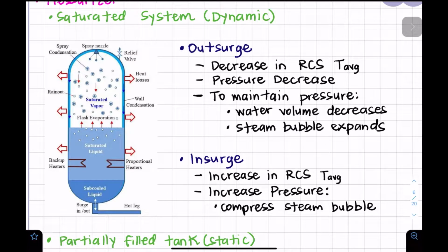The control heater current will increase as the pressure decreases. So we're going to have the heater on, right? Because we are decreasing the temperature. We're converting more saturated vapor into saturated liquid. So if we really need to maintain the same pressure in the pressurizer, we need to start turning on the heaters, right? Because we need to go back up to the same pressure that we were before.